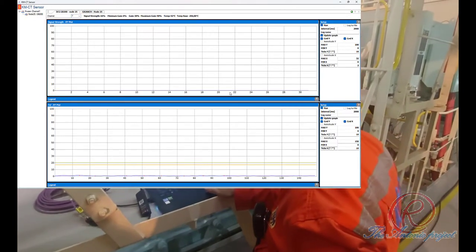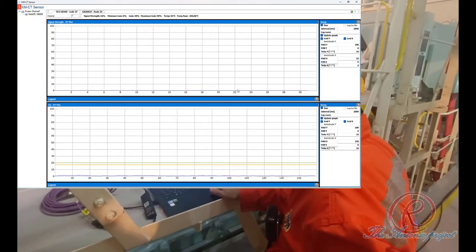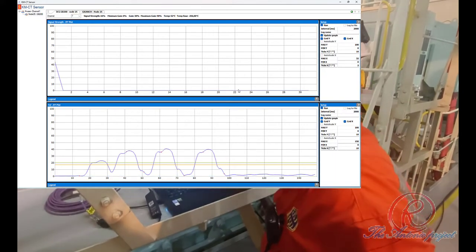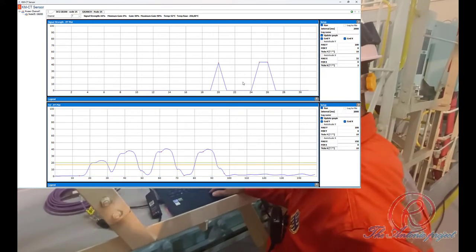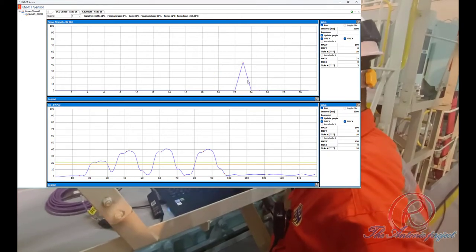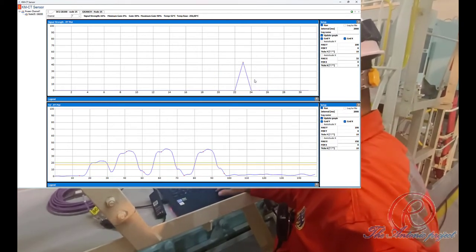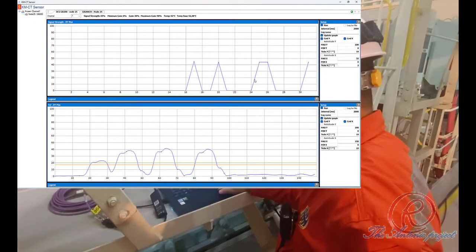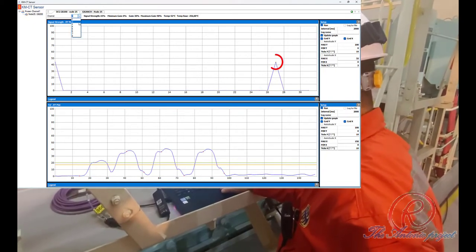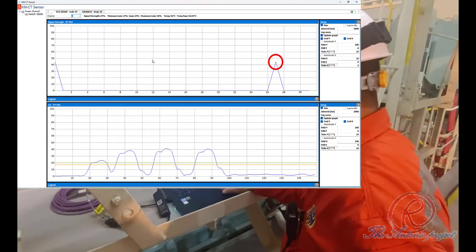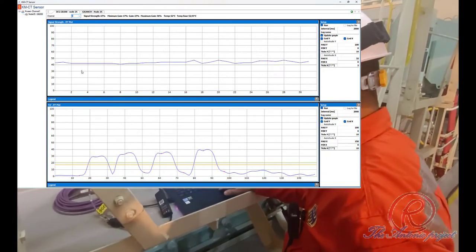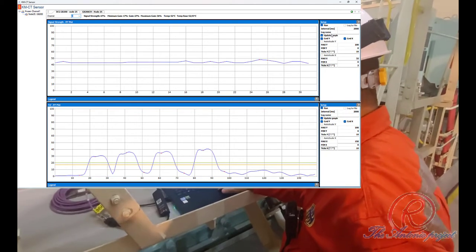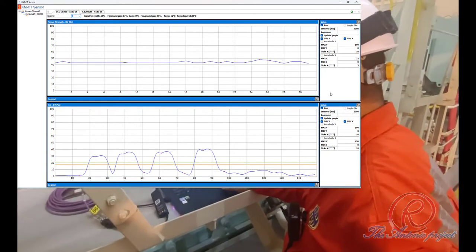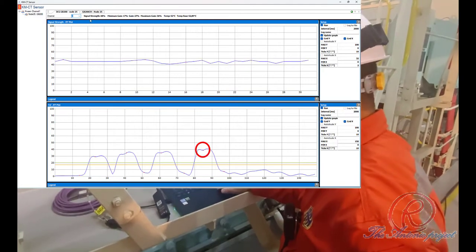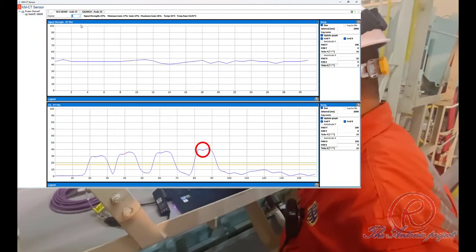Viewing sensor signal strength and shape. It is possible to view the current signal strength of the selected channel and also the amplitude and shape of the echoes returned to the SPU from the sensor in question. The top window, called signal strength, shows the current signal level of the sensor signal. The red dots show the samples used to automatically adjust the receiver gain. The lower window shows the amplitude of the signal reflected back from the sensor. The red dots in this graph are used to validate the received sensor signal.